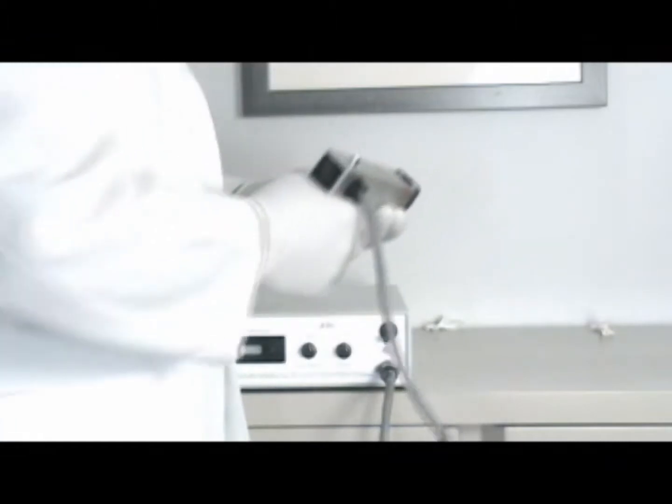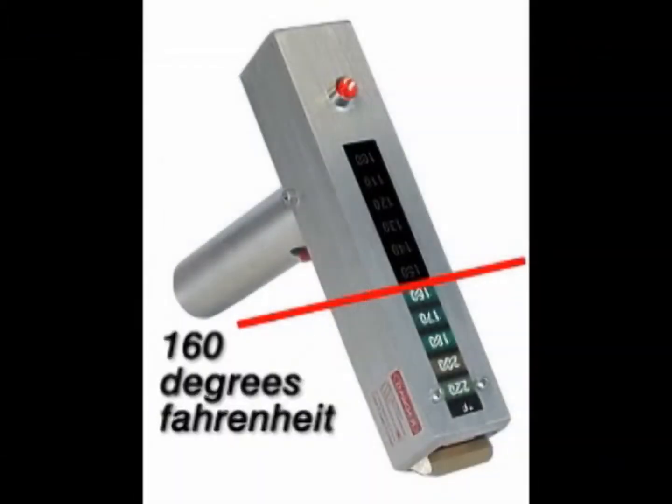This will keep your laser operating at optimal performance. Your temperature gauge will turn black up to the correct number. Do not allow your diode to exceed 160 degrees.